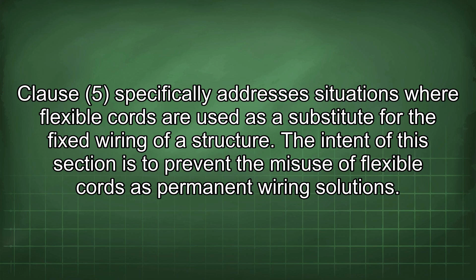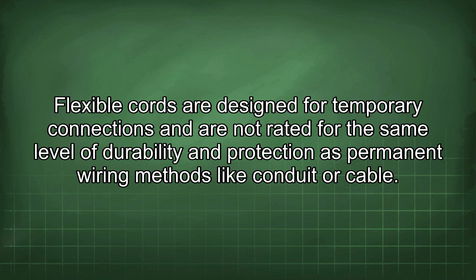National Electrical Code Section 400.8 covers uses not permitted for flexible cords and cables. Clause 5 specifically addresses situations where flexible cords are used as a substitute for the fixed wiring of a structure. The intent of this section is to prevent the misuse of flexible cords as permanent wiring solutions. Flexible cords are designed for temporary connections and are not rated for the same level of durability and protection as permanent wiring methods like conduit or cable.